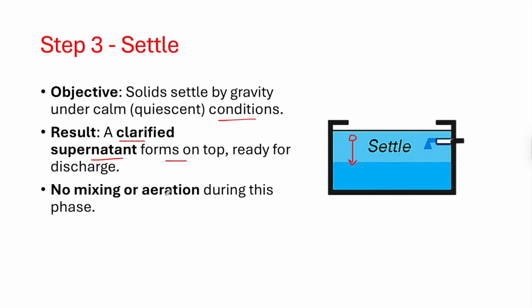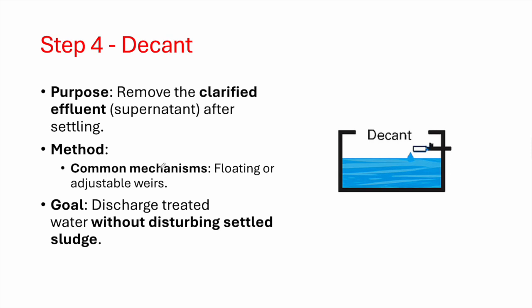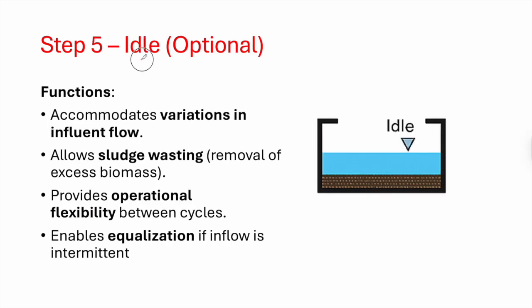In the decant phase, the clarified effluent is removed after settling using a floating or adjustable weir decanter. The goal is to discharge the treated water without disturbing the settled sludge. The clear water is then moved calmly to tertiary treatment — chlorination.